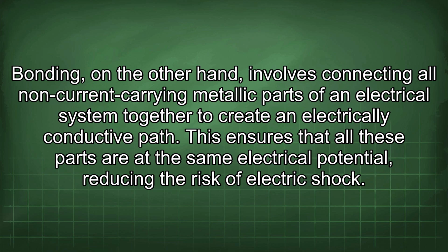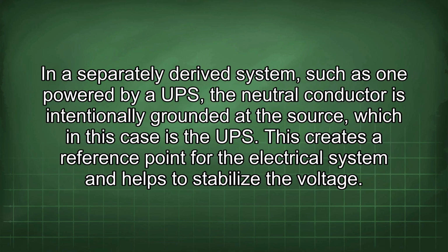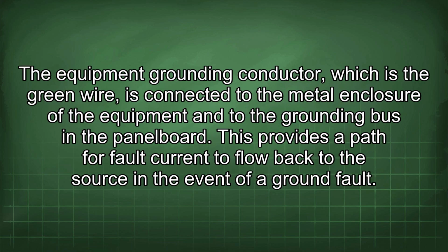electric shock. In a separately derived system, such as one powered by a UPS, the neutral conductor is intentionally grounded at the source, which in this case is the UPS. This creates a reference point for the electrical system and helps to stabilize the voltage. The equipment grounding conductor, which is the green wire, is connected to the metal enclosure of the equipment and to the grounding bus in the panel board. This provides a path for fault current to flow back to the source in the event of a ground fault.